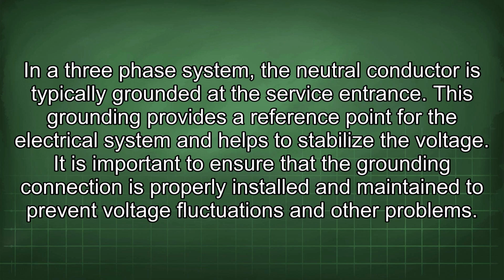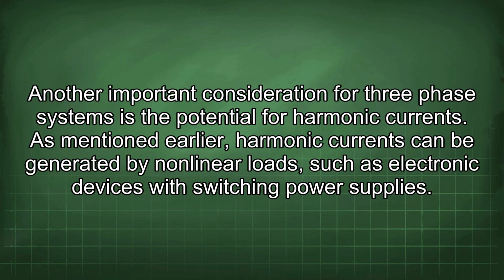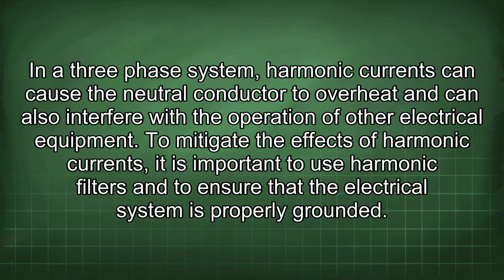It is important to ensure that the grounding connection is properly installed and maintained to prevent voltage fluctuations and other problems. Another important consideration for three-phase systems is the potential for harmonic currents. As mentioned earlier, harmonic currents can be generated by nonlinear loads, such as electronic devices with switching power supplies. In a three-phase system, harmonic currents can cause the neutral conductor to overheat and can also interfere with the operation of other electrical equipment. To mitigate the effects of harmonic currents, it is important to use harmonic filters and to ensure that the electrical system is properly grounded.